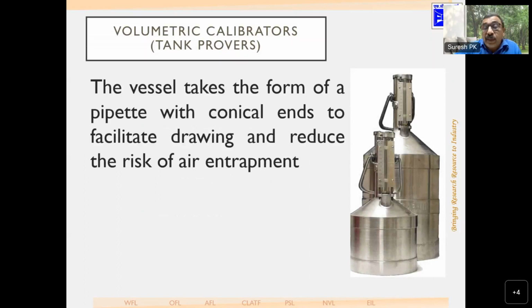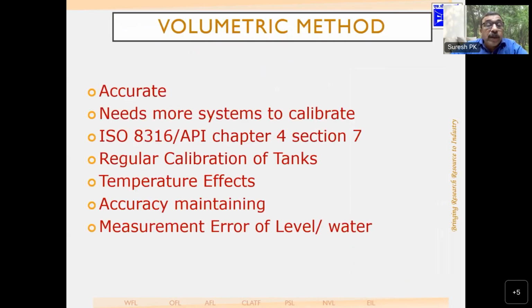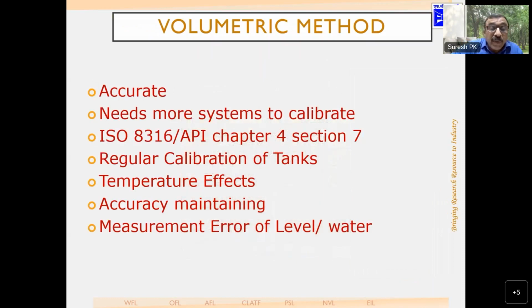Tank provers, you must have seen. The vessel takes the form of a pipette with a conical end to facilitate the drawing and reduce the risk of air entrapment. Standard volumetric tank provers are used. They are accurate, but they need more systems to calibrate. Regular calibration of these tanks is required. We have temperature effects probably on the calibration. Maintaining accuracy is a tough task. Measurement error of the level of water in the neck is another uncertainty which it can encounter.